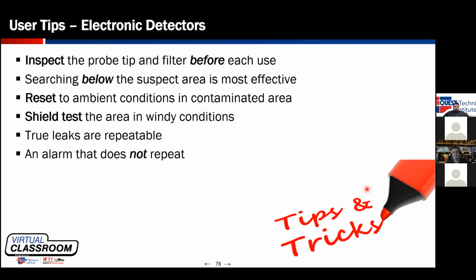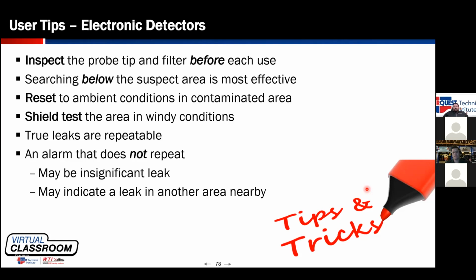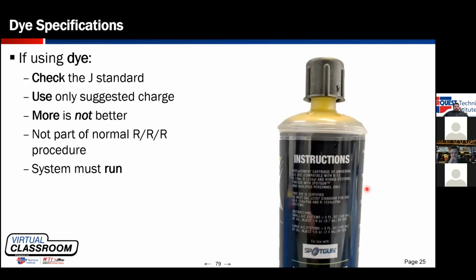A leak should be repeatable. If that is a true leak, I should be able to clear it, go back to it, and find the leak again. If you have something that you trigger and it's not repeatable, it's either a leak that is not significant or you may be picking something else up. We talked about dye, that if you're going to use dye, make sure it meets the standards. Do not use more dye than is recommended.